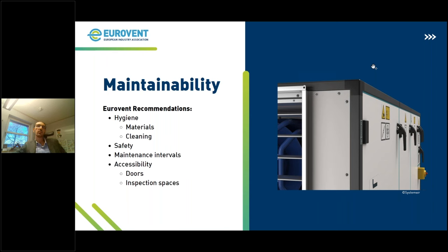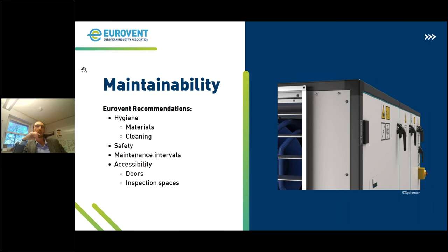For cleaning, every component in the unit should be accessible — I will explain accessibility separately in the next slide. To clean the unit itself, a neutral cleaning agent or alcohol-based disinfectant should be used on the inner surfaces of the unit, to ensure safe maintenance. For the casing, the casing and its surfaces should not have any sharp metal sheets — in design and production of the unit, this must really be paid attention.